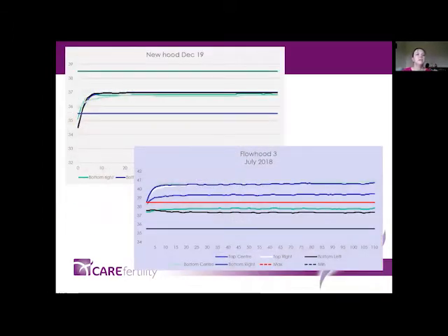So yeah, this was just an example to show you that we had a flow hood that was particularly old, and we get it in all of the work hoods, but sometimes you've got patches where it's a bit cooler, and it's always a bit of a compromise trying to get the perfect temperature across the work area.